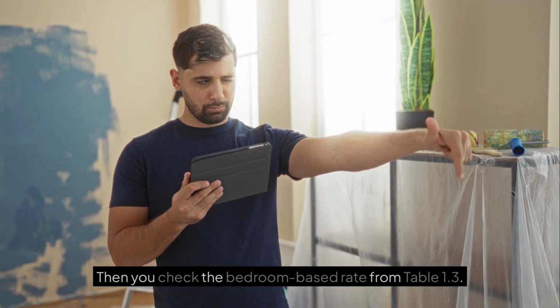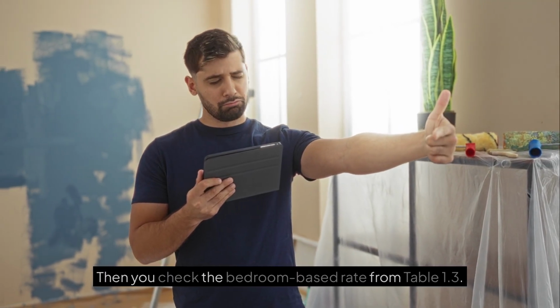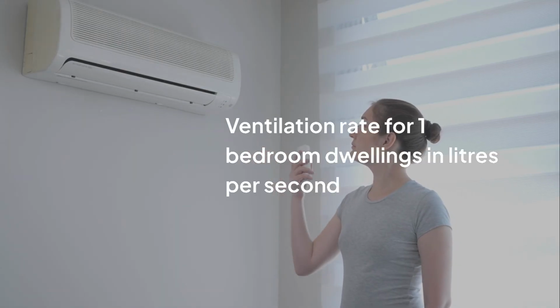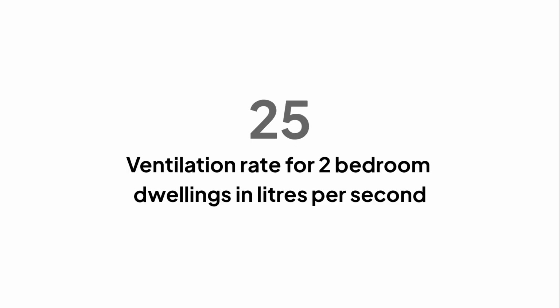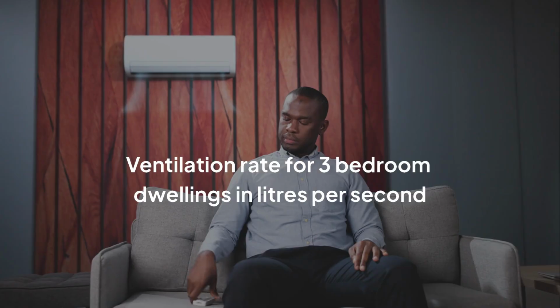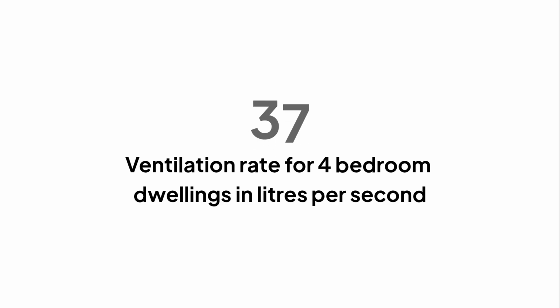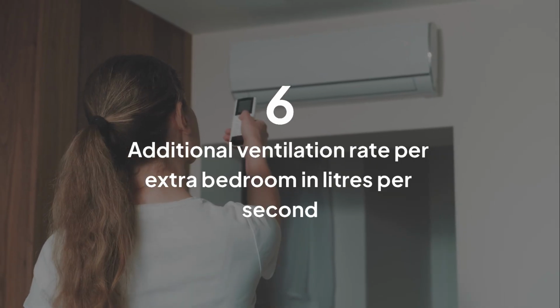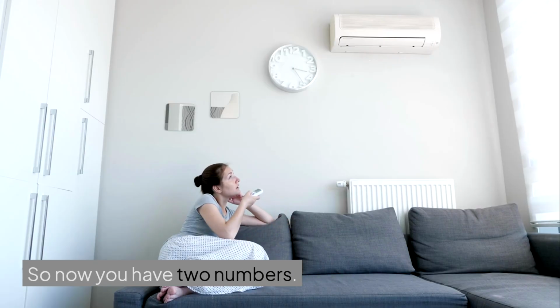That gives you one candidate whole dwelling ventilation rate. Then you check the bedroom-based rate from Table 1.3. The table gives 1 bedroom equals 19 litres per second. 2 bedrooms equals 25 litres per second. 3 bedrooms equals 31 litres per second. 4 bedrooms equals 37 litres per second. 5 bedrooms equals 43 litres per second. And for each additional bedroom above that, you add 6 litres per second.